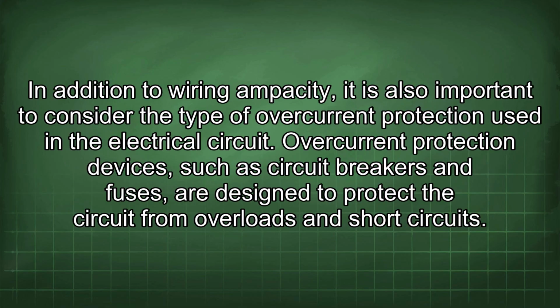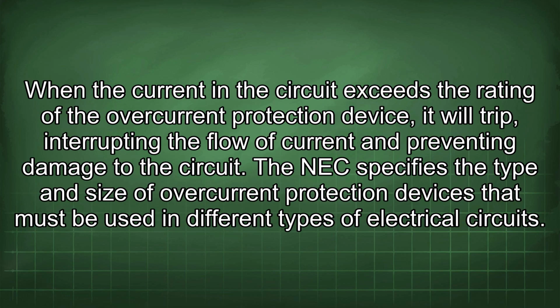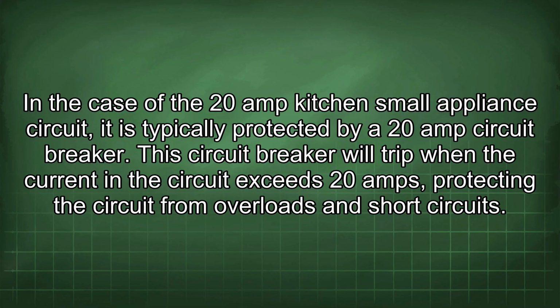In addition to wiring ampacity, it is also important to consider the type of overcurrent protection used in the electrical circuit. Overcurrent protection devices, such as circuit breakers and fuses, are designed to protect the circuit from overloads and short circuits. When the current in the circuit exceeds the rating of the overcurrent protection device, it will trip, interrupting the flow of current and preventing damage to the circuit. The NEC specifies the type and size of overcurrent protection devices that must be used in different types of electrical circuits. In the case of the 20 amp kitchen small appliance circuit, it is typically protected by a 20 amp circuit breaker.